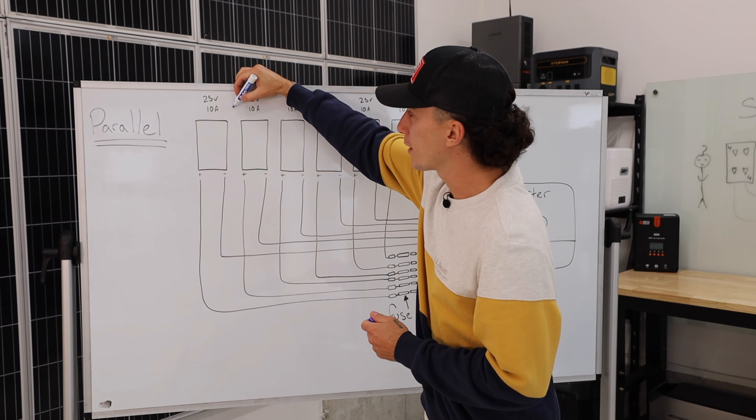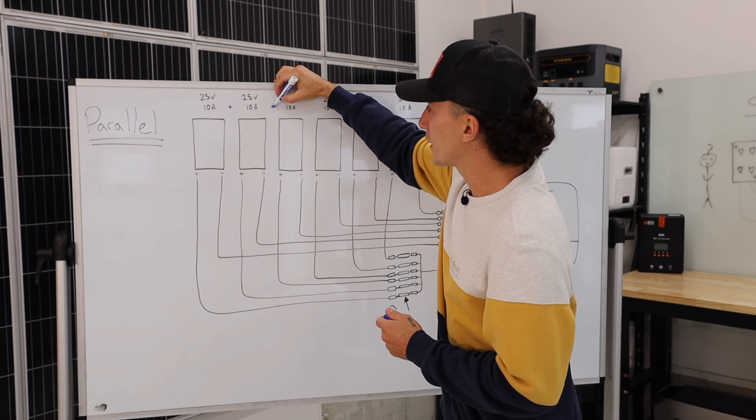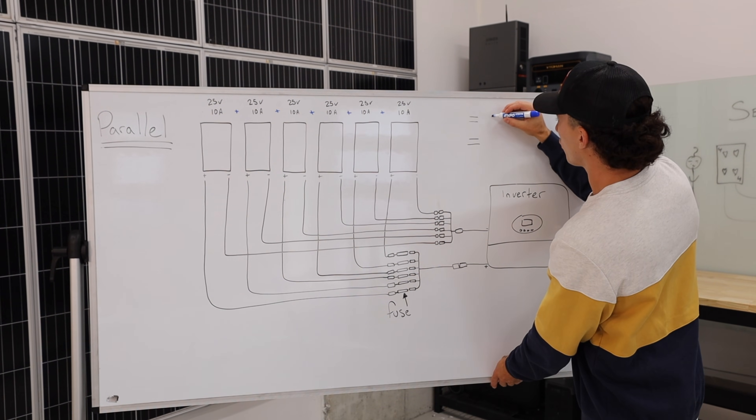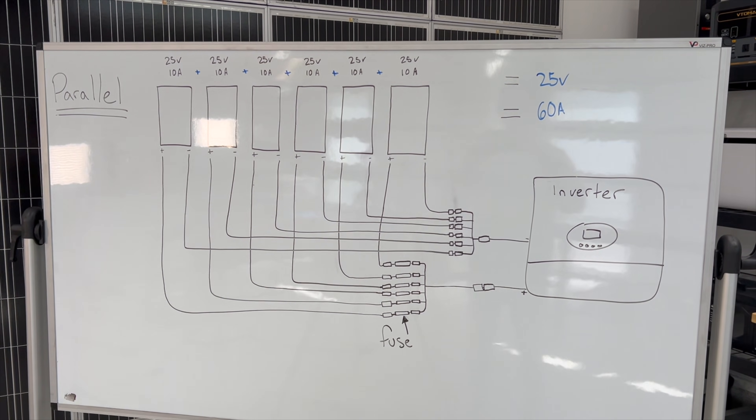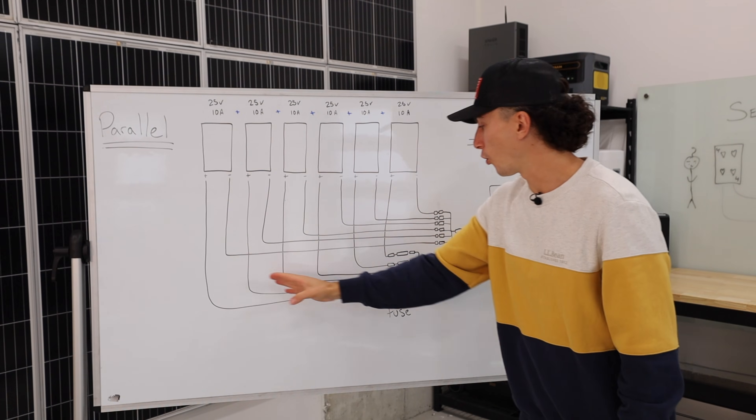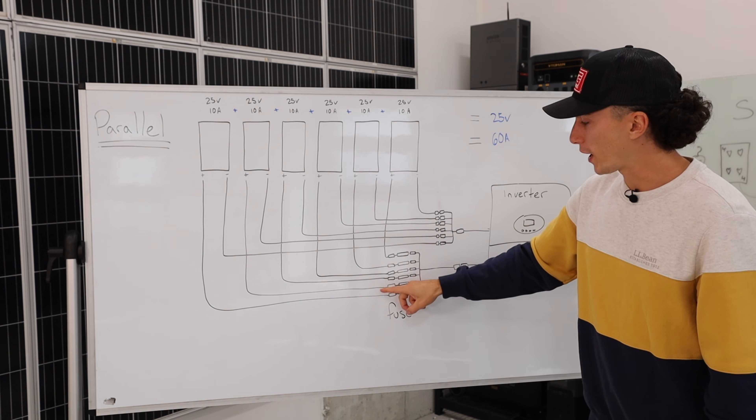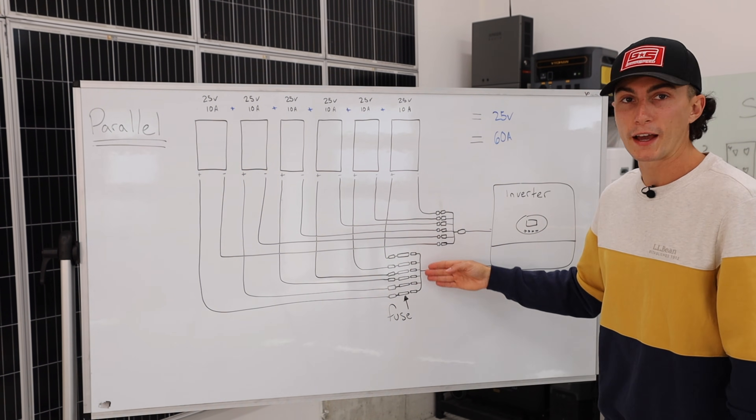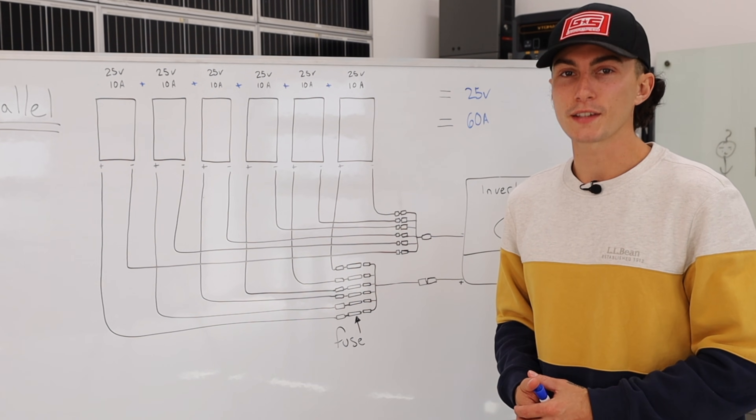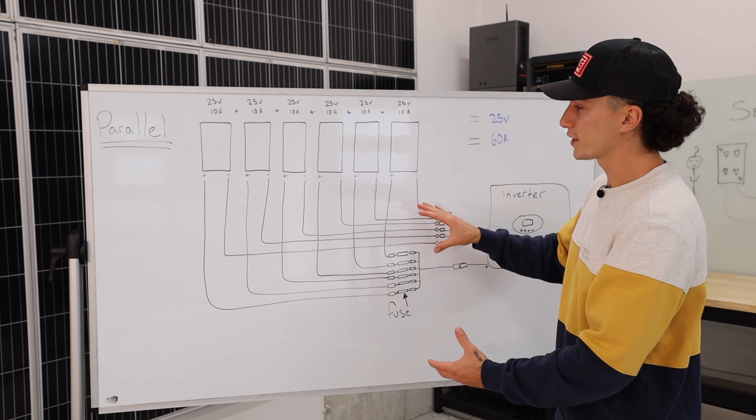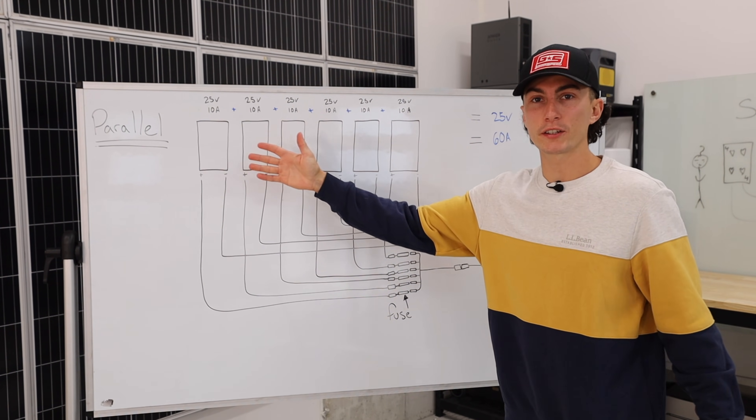If you were to add all this up for this array, you would actually only add the amps and the volts stay the same. You actually have a total of 25 volts for this array, but you would have 60 amps because in parallel, when all the wires come down here carrying 10 amps, they all combine—you now have 60 amps.